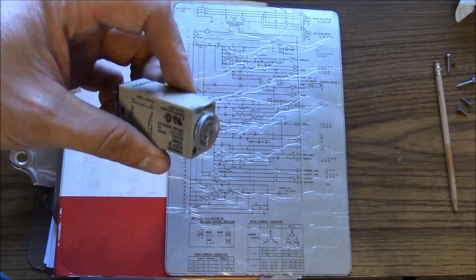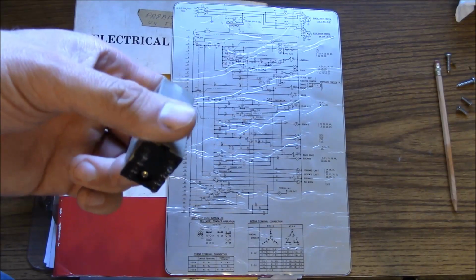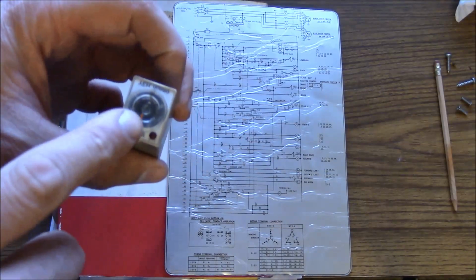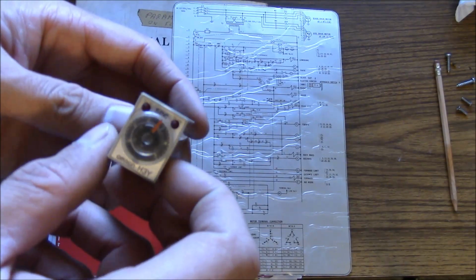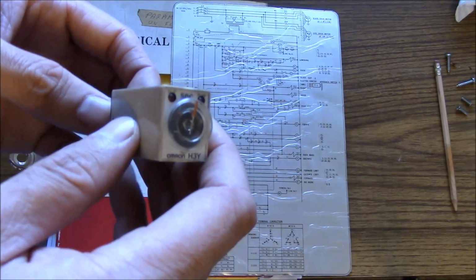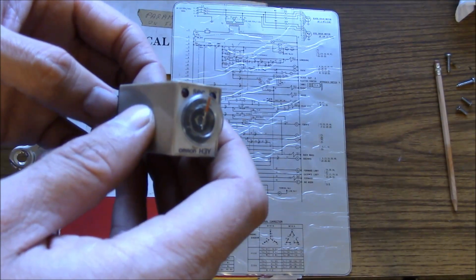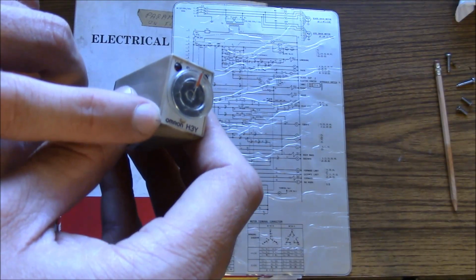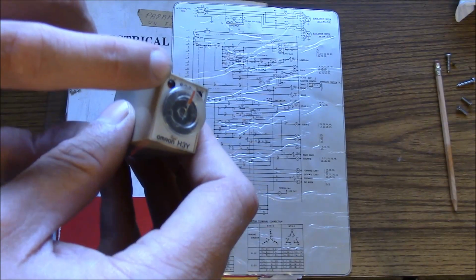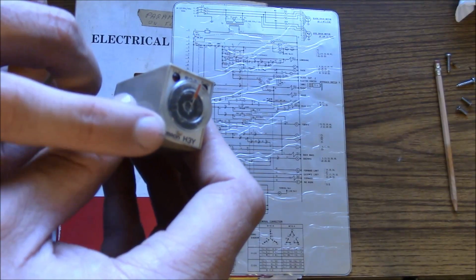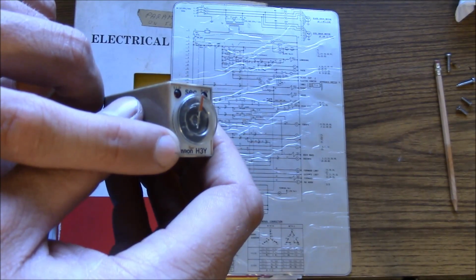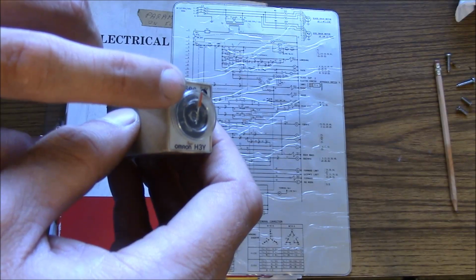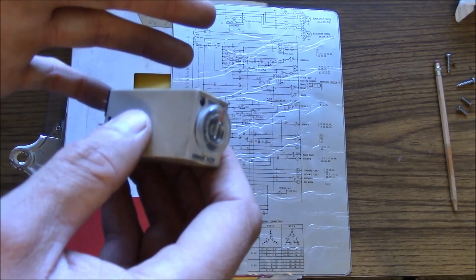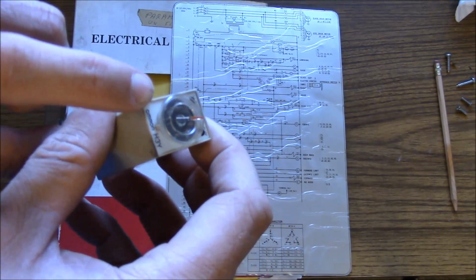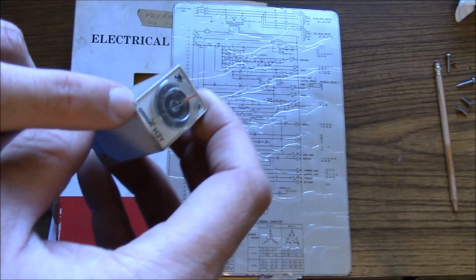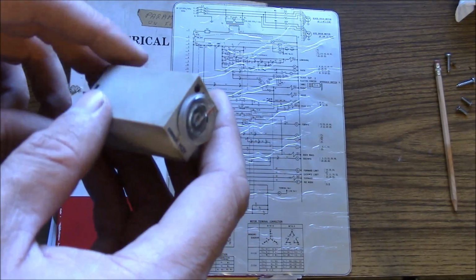So this is another kind of relay here. This is a timer relay, and it basically functions exactly the same as a normal relay, except that it has an adjustable timer here. Typically these can be set for several different functions, but the most common is a time on delay, where the coil is energized and then the relay takes some amount of time to actually make contact, or a time off delay, where the coil is de-energized but it takes a certain amount of time for the contacts to actually open. So the contacts hold after it loses charge to the coil. There are other functions that they can do, but that's the most common.